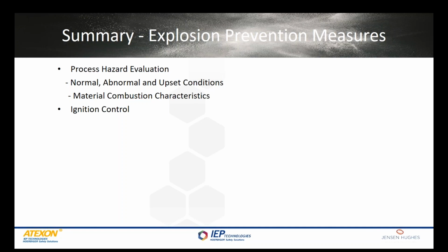What type of ignition control has been employed at the facility? Do you have spark detection and suppression on conveying ducts and drop chutes where an ignition source could be generated and then transmitted to a different part of the facility where it could create an explosion? Is there proper electrostatic bonding and grounding? We all know from the previous information that there's a very low ignition energy tolerance for dry wood products, and electrostatic ignition is certainly enough ignition energy to initiate an explosion.